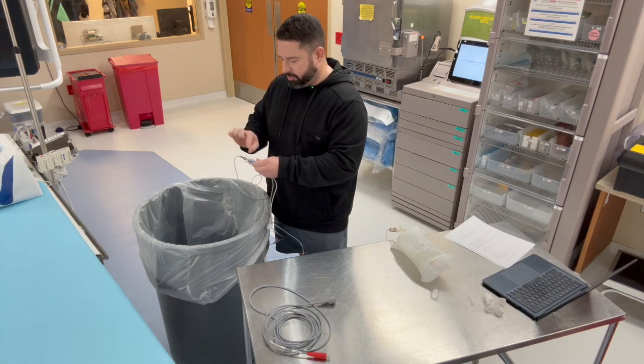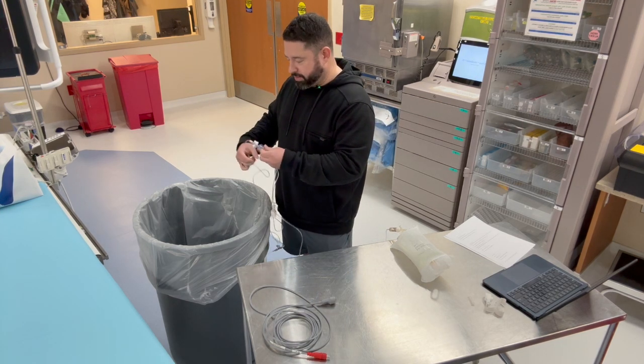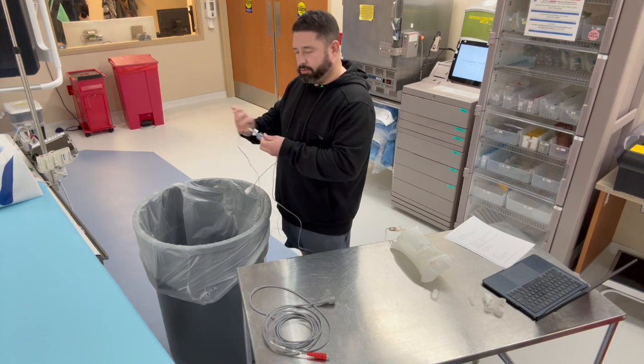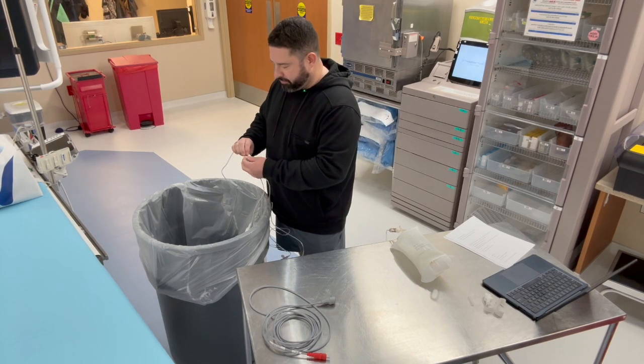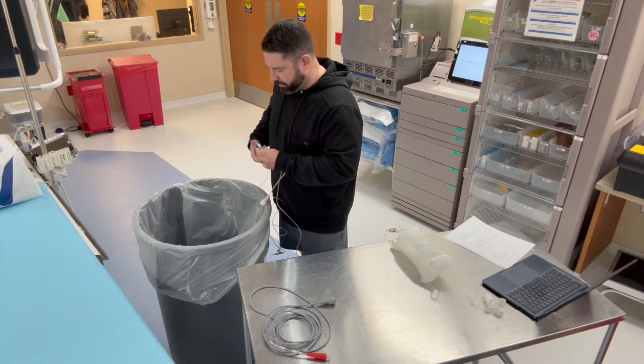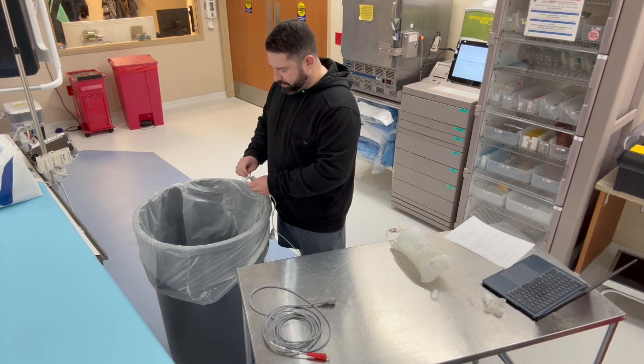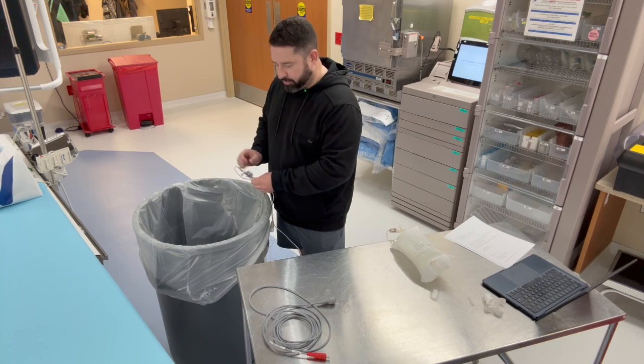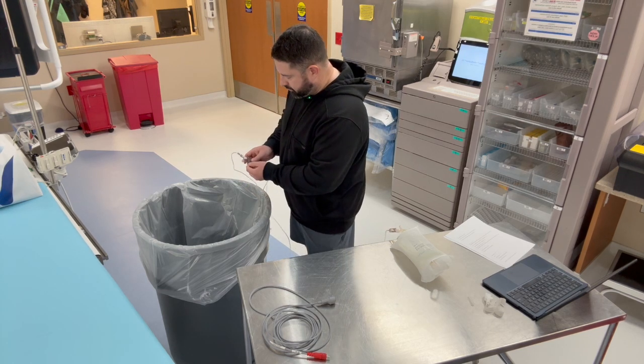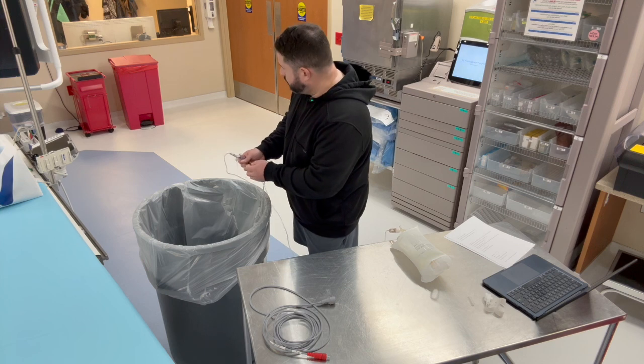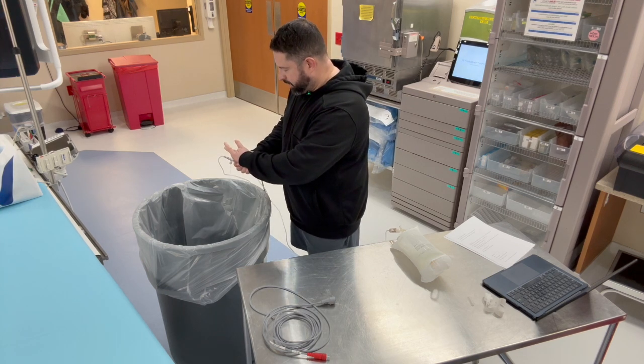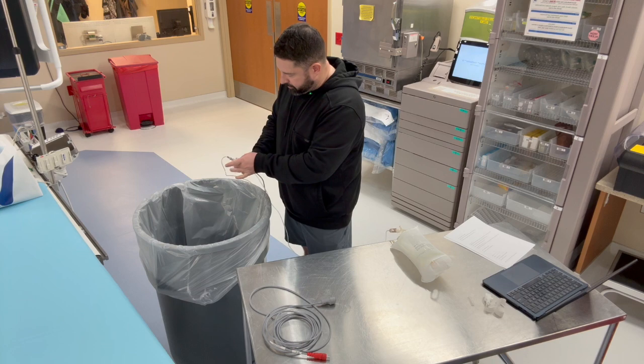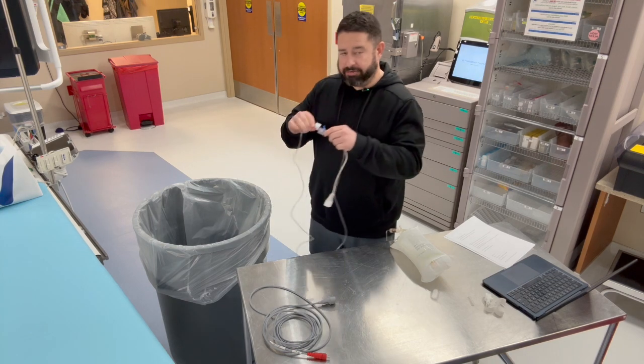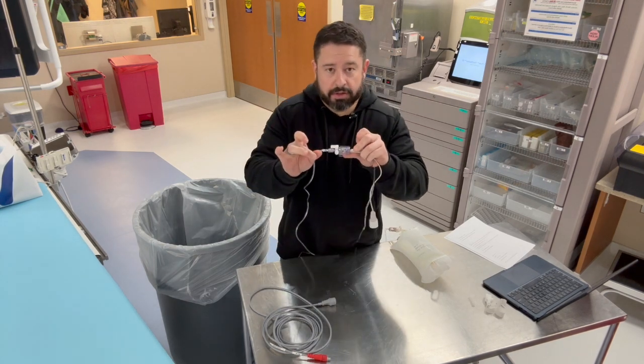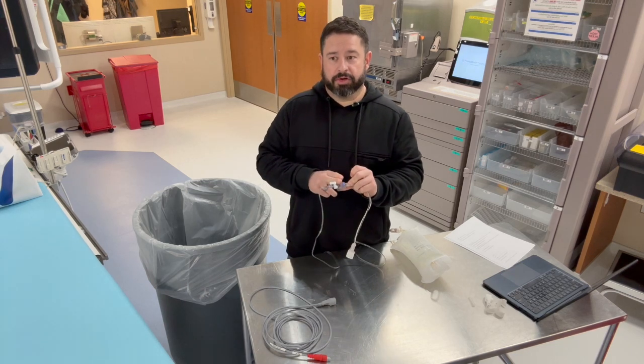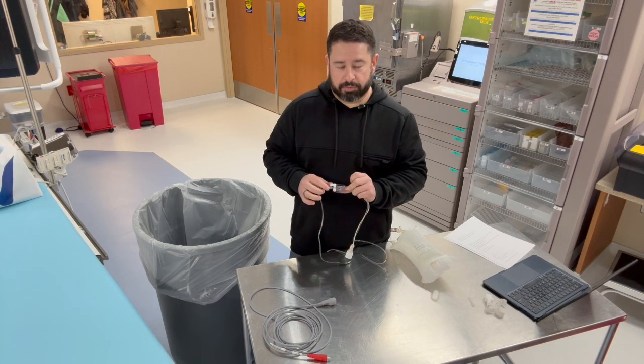I have the stopcock off to the patient. It's off to the patient. This is a vented cap. We can leave that on. And then we can pull the tab, and that will allow fluid to move through the transducer. At this time, what I will also do is tap the transducer just to make sure there's no air. If you have any air bubbles in your transducer here, it can cause variations in your pressure waveform that you're looking at.